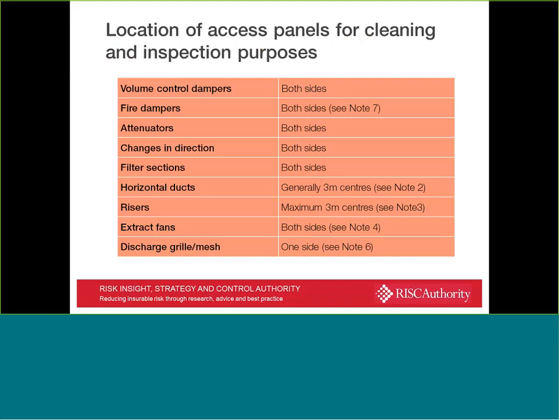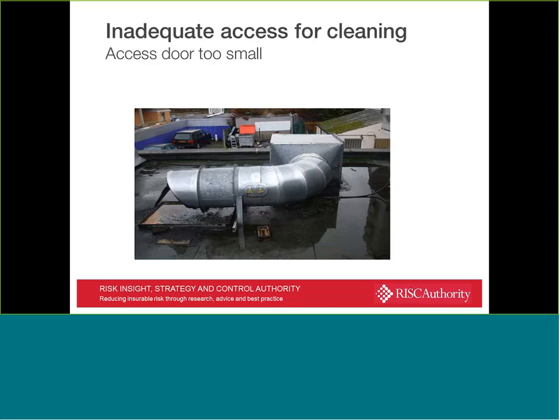In order to ensure that cleaning can be done effectively, you'll find this guidance in a number of locations. This is taken from the BESA publication TR19, which I mentioned earlier, which describes the location of access panels for cleaning and inspection purposes, highlights the various areas of concern, and describes exactly where the access panels should be. You'll notice there where it talks about horizontal ducts, generally at 3 metre sections, and in risers again, a maximum of 3 metre centres, to ensure that all areas of the ductwork can be effectively cleaned.